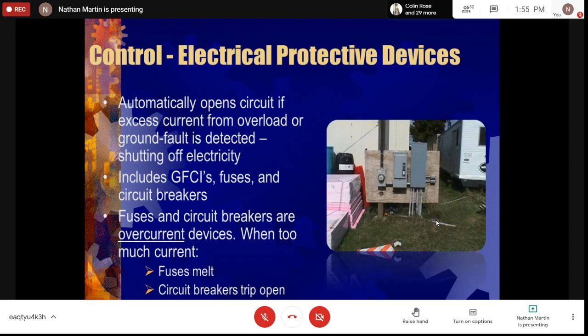Now the reason for this is that a lot of times, because of the cost of the GFCI outlet, when it goes bad, people tend to want to change it and put in a regular socket outlet, saying the regular outlet works just the same. No, if you remove it, you lose a certain amount of protection from ground faults. If it's not connected properly, it won't work properly, so you must ensure the earthing is connected in the building, and that the earthing for the GFCI breaker and outlet is properly connected. Without that, it will not trip on ground faults.